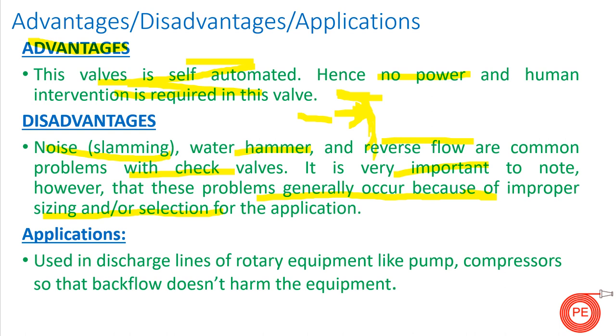Applications: check valves are used in discharge lines of rotary equipment like pumps and compressors so that backflow doesn't harm the equipment. In the case of a pump, backflow may strike the impeller and destroy its vanes. Similarly, in a compressor, back-flowing air can impact and destroy the equipment.